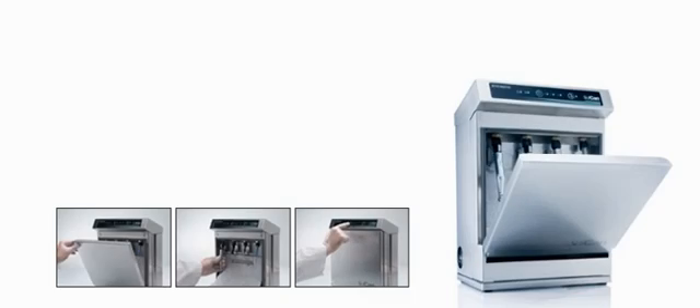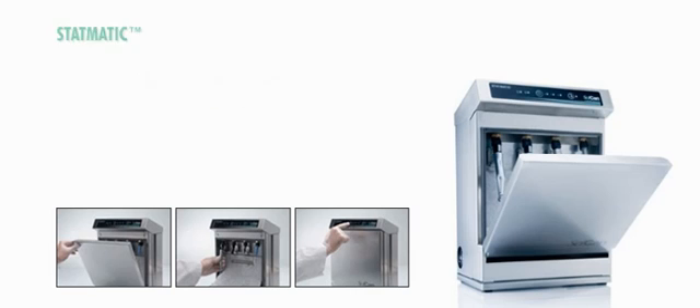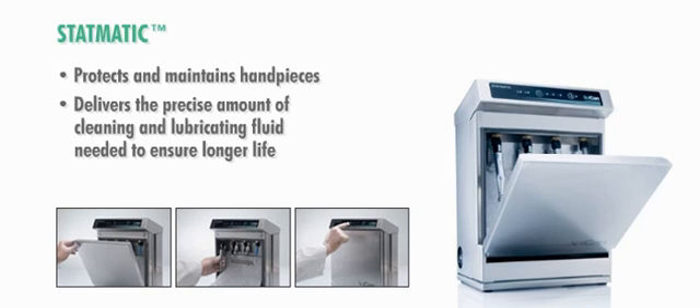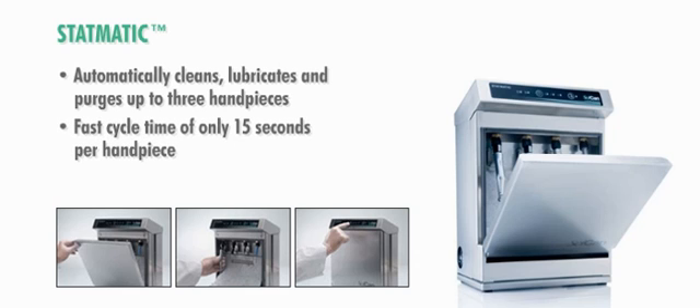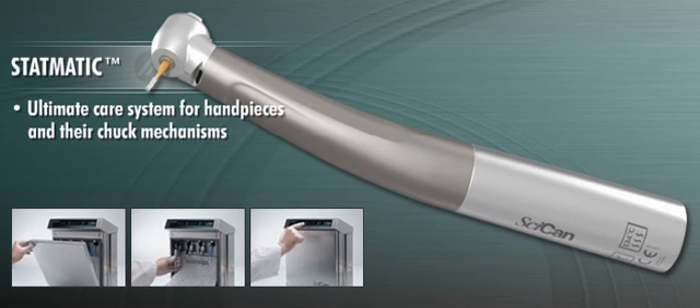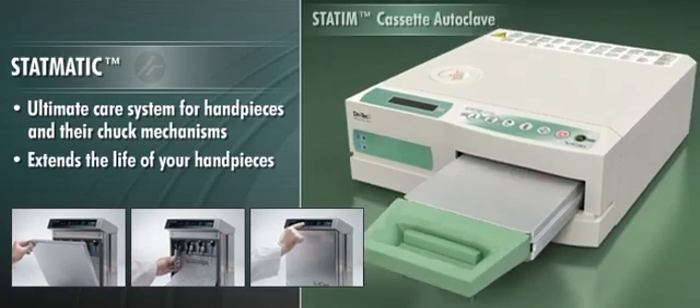If not properly cleaned and maintained, even the finest handpieces will wear out sooner than they should. SciCan STATMATIC protects and maintains your handpieces by delivering the precise amount of cleaning and lubricating fluid needed to ensure longer life. STATMATIC automatically cleans, lubricates, and purges up to three handpieces with a fast cycle time of only 15 seconds per handpiece and includes a maintenance mechanism that provides the same protection for the chuck. The ultimate care system for handpieces and their chuck mechanisms, STATMATIC extends the life of your handpieces, especially when used in conjunction with a STATIM cassette autoclave.